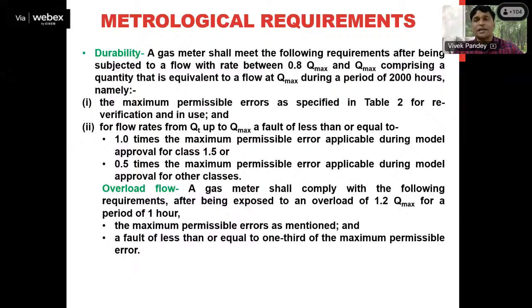So suppose a gas meter is there and its maximum flow rate is specified as 1000 liter per hour. During the durability test, we can make the transaction of gas at a flow rate between 800 liter per hour and 1000 liter per hour, and for how long? For 2000 hours continuously. After running it for 2000 hours, we will again perform its accuracy test. If during that accuracy test it is giving the same accuracy, that means the error is within the prescribed limit of tolerance in our rule, we can say that it is durable, or that it has passed the durability test.